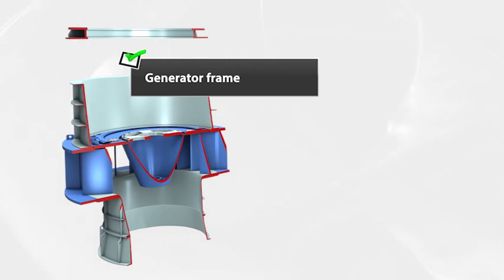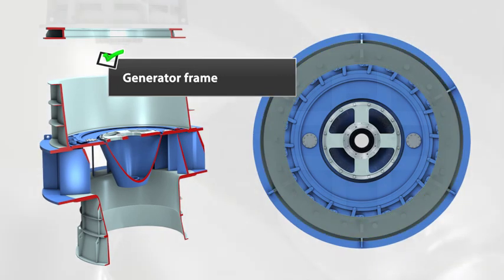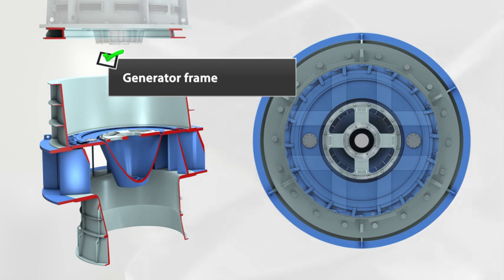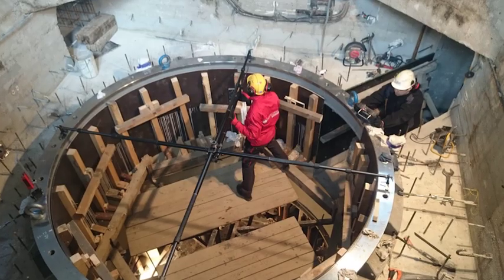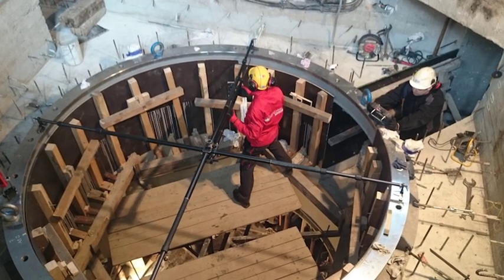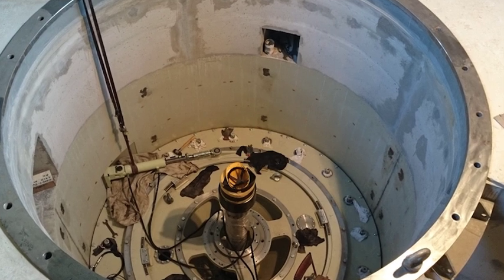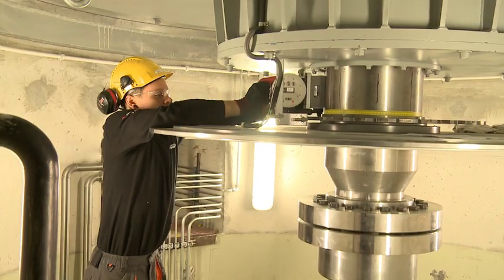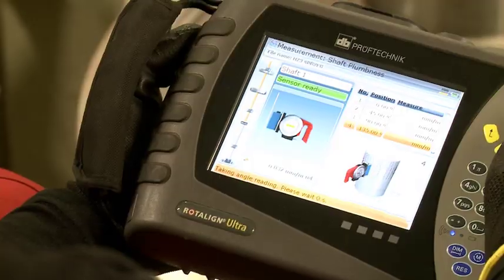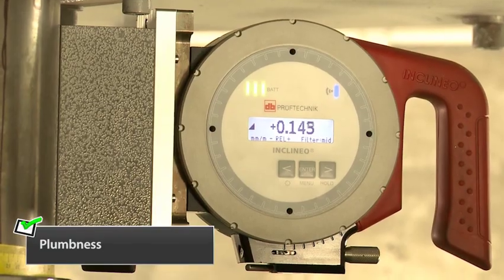The same alignment procedure and set of measurements used for the turbine chamber are applied after installing the generator frame. We check the concentricity of the generator frame bore in relation to the turbine chamber, and then perform levelness and flatness adjustments of the generator ring. We then verify the plumbness of the shaft rotational axis using Inclineo and the Rotalign Ultra hydropower application.